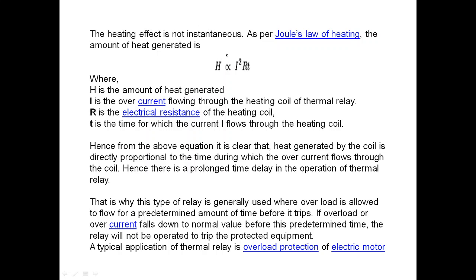The heating effect is not instantaneous. As per Joule's law of heating, the amount of heat generated H is proportional to I squared R T, where H is the amount of heat generated, I is the overcurrent flowing through the heating coil of the thermal relay, R is the electric resistance of the heating coil, and T is the time for which the current I flows through the heating coil. Hence, from the above equation, it is clear that the heat generated by the coil is directly proportional to the time during which the overcurrent flows through the coil.